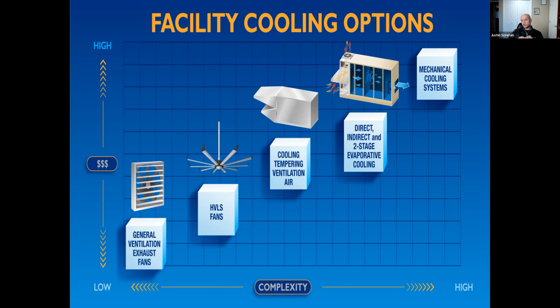So we can actually use our evaporative cooler as a first stage of cooling, a temperature depression, if you will. We cannot specify a set point in a building based off evaporative cooling technology because it's totally dependent on what the outside air conditions are doing. So what we can use an evaporative cooler for is, let's say, 90% of the load. Then that last 10% of the load, or the trim load, if you will, we can trim with a mechanical cooling system. Doesn't matter what it is.